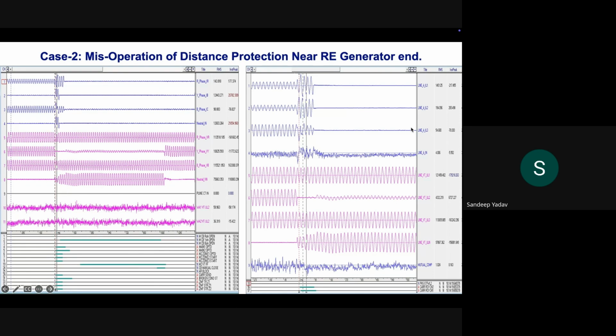on the RE generator side, for the same fault, the grid side is feeding 12 kiloampere. However, the RE generator end is feeding only 145 amps, 194 amps, and 54 amps. So these are very small currents. The magnitude is so small that the phase to ground loop of the distance relay, which is located on the RE generator side, will not pick up. So if you take a look at the digital channels of this relay, it has not operated, because there is not sufficient current at the time of the fault for the relay to detect the fault, right? So in this case, the relay has not operated. So grid side relay has operated on the left hand. However, the RE generator side relay has not operated at all.